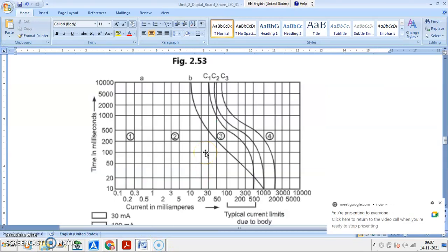So in healthy condition, the sum of the currents is equal to 0, or there is no current through neutral. When the sum of the currents is 0, there is no fault, no earth leakage detected. So currents are balanced, but whenever there is a fault, current is not balanced. Current will flow through neutral, through earth. So leakage is there. So current imbalance is detected, and the RCCB is tripped if this current is more than the set value. Right?